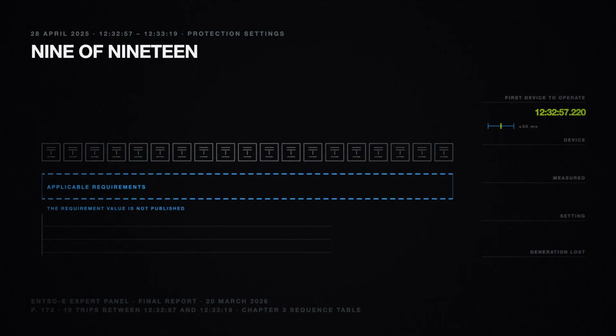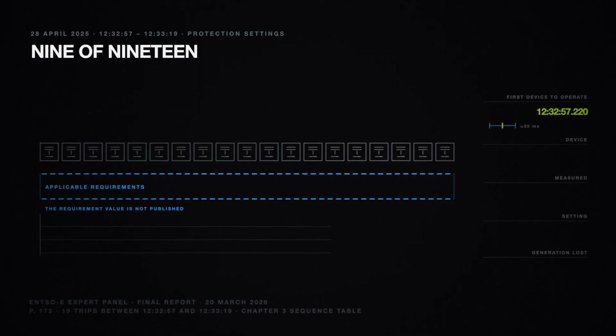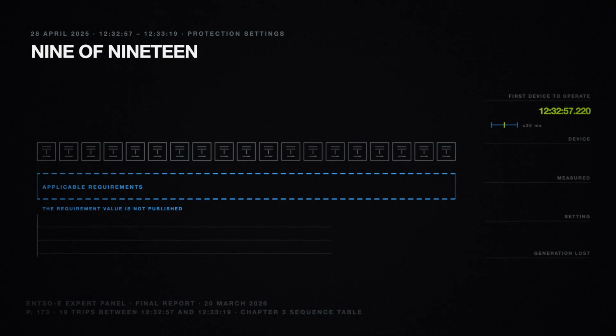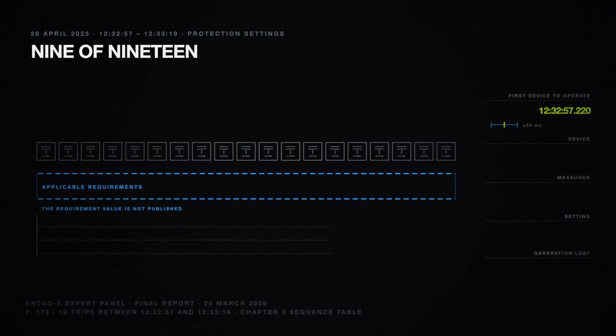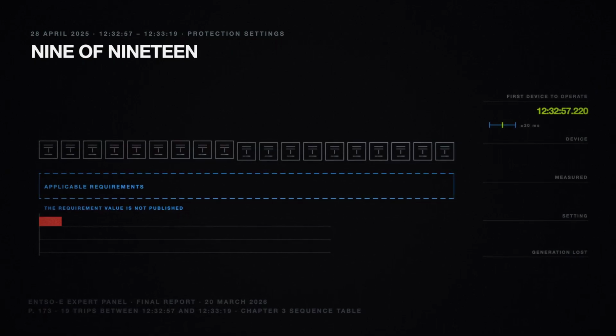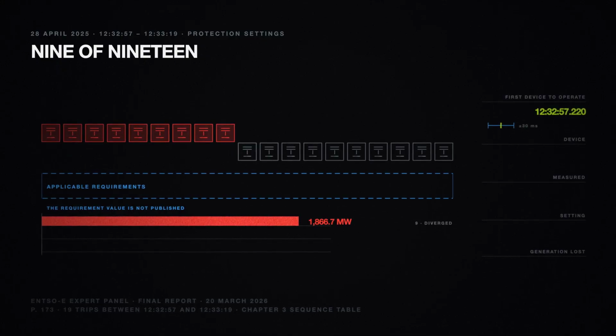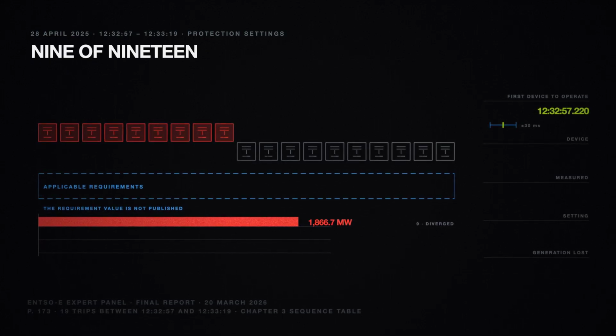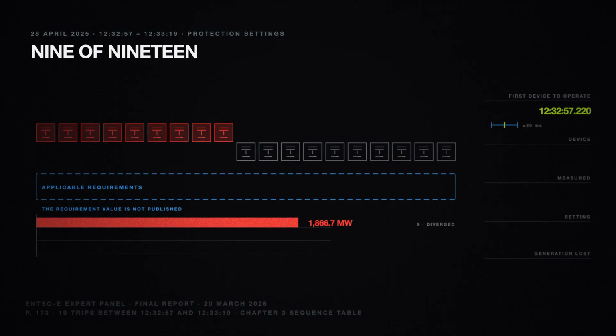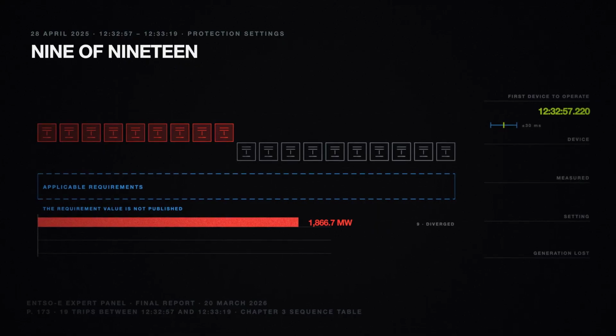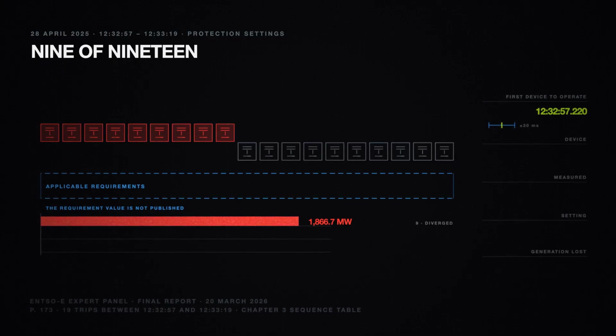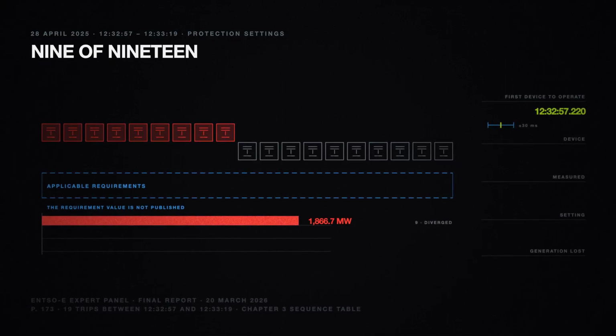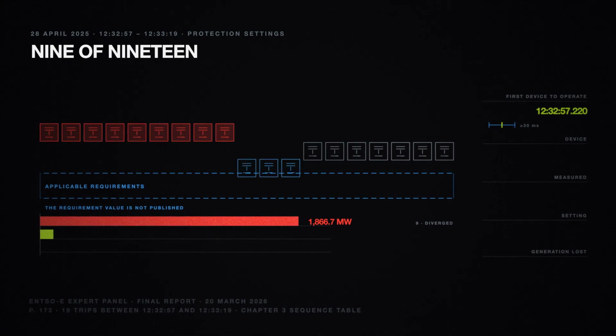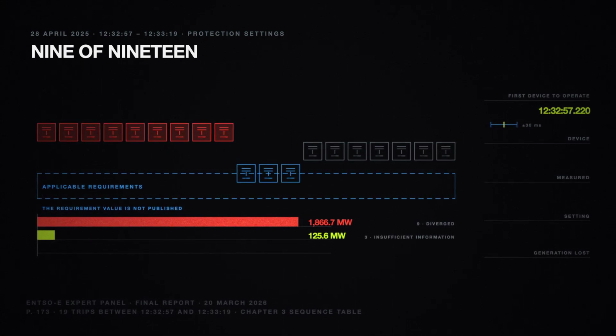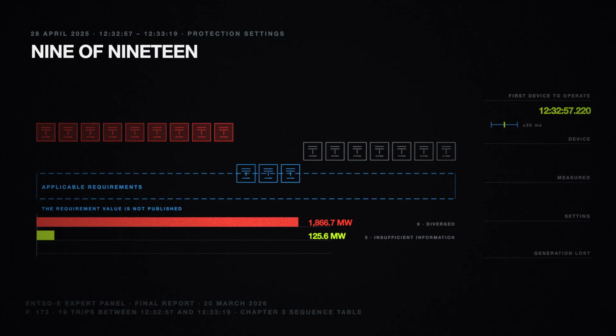And then the sentence that follows it. All of the settings received diverge from the applicable requirements. All of them, not most of them. Then the classification. Of the 19 trips detected between 12:32:57 and 12:33:19, 9 of them diverged from the applicable requirements and caused the loss of 1,866.7 megawatts. For 3 of the trips, 125.6 megawatts, there is insufficient information.